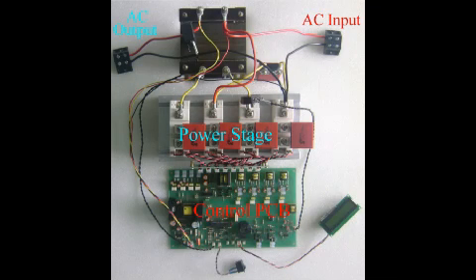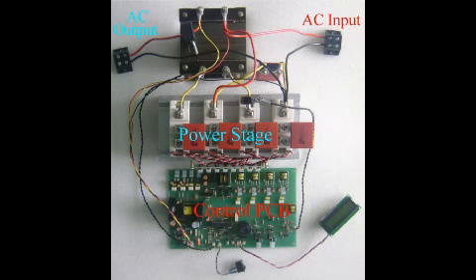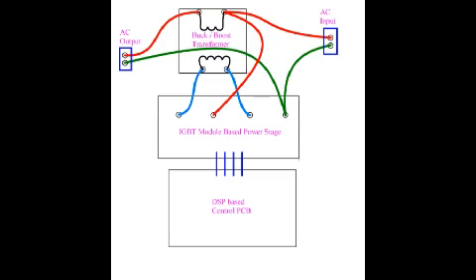This is the static voltage stabilizer using PWM. You can see the IGBT power stage, control PCB, LCD display, AC input and AC output — the neutral is common between them. There is a buck-boost transformer which adds and subtracts voltage in series with the AC input, so we can add or subtract voltage on the phase line to keep the output voltage steady.